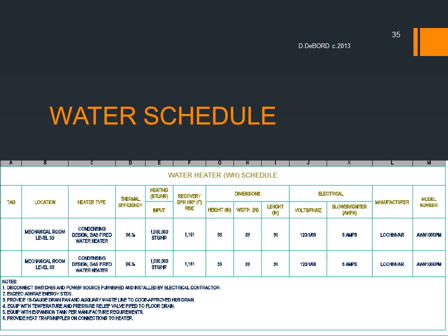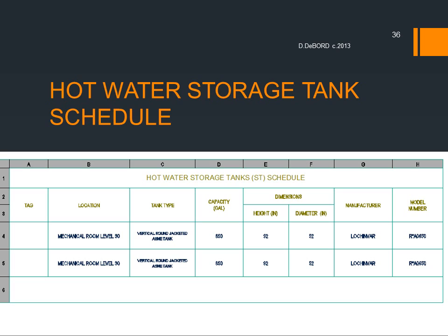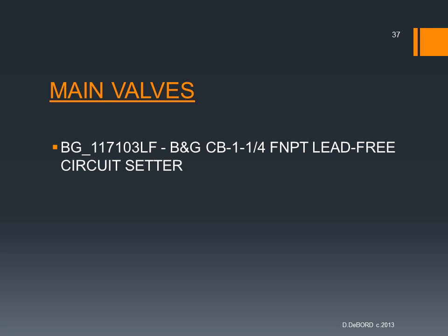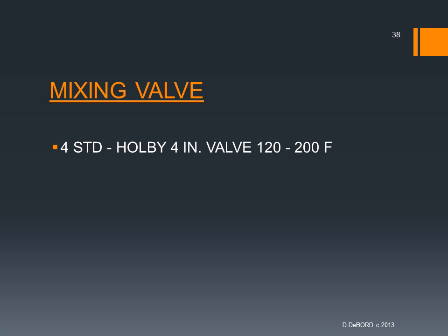Here's the water heater schedule that goes with that diagram. We have 2 water heaters at 96% efficient, 1 million BTUs each, and the rest of the nomenclature's there. We have a few notes included also. Here's the storage tank schedule. We had 2 650-gallon storage tanks, and this has a few of the bits of the nomenclature for those. Then we also included on the drawings things like the main valves, circuit setters, the mixing valves. We use the Holbys. Holbys are very good for mixing at the actual water heater, not at the fixture, but at the heater.